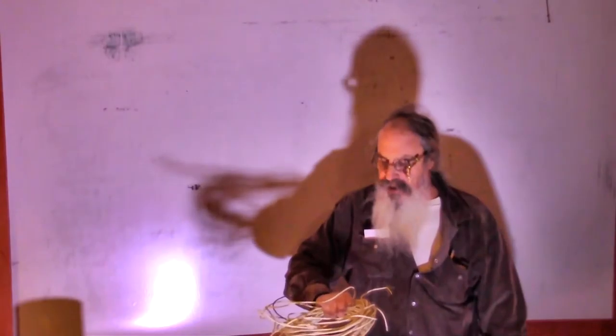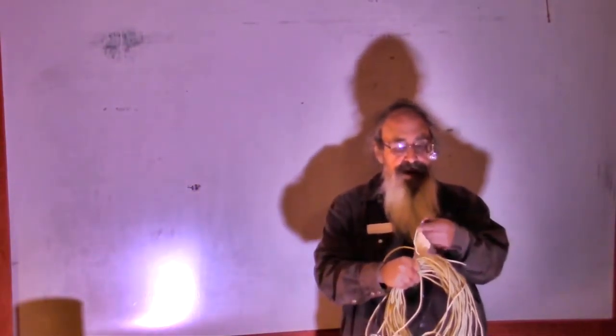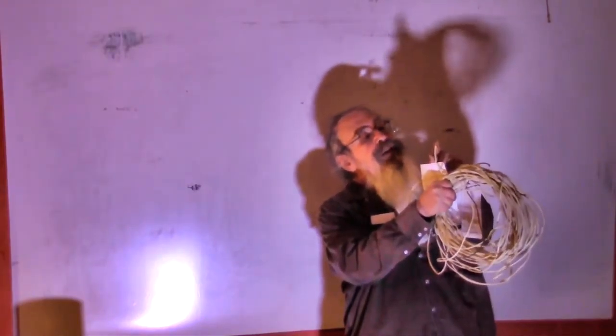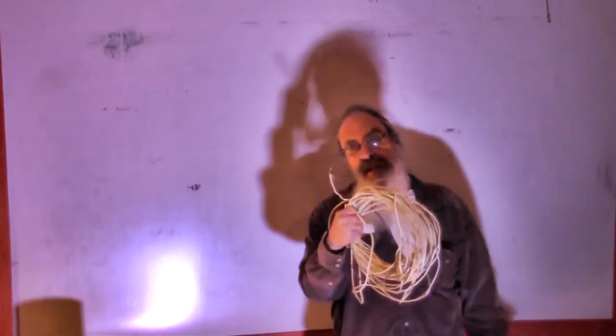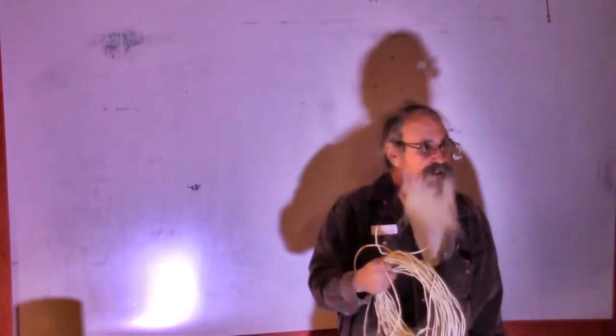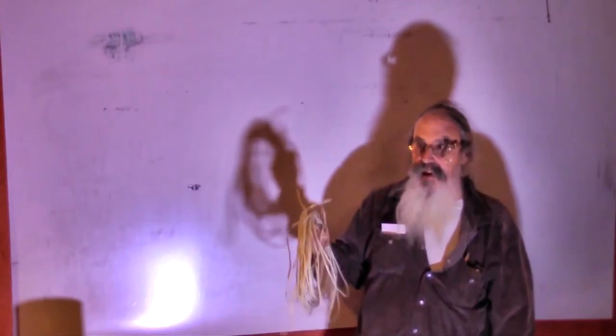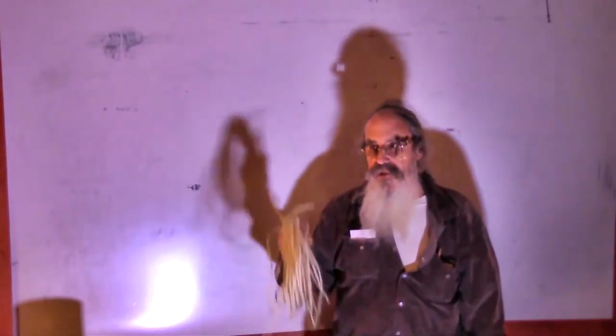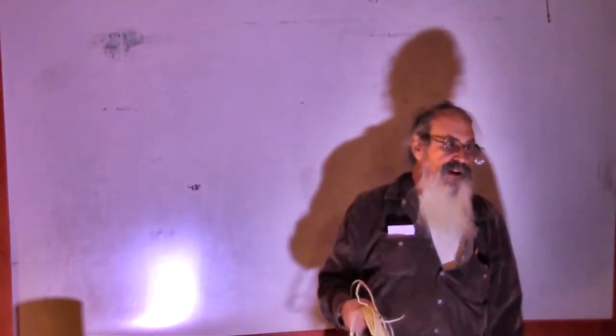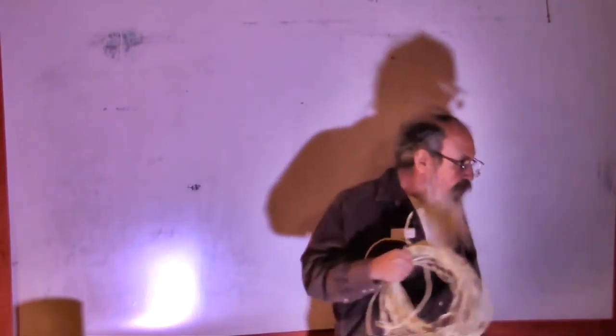So if you want to go a little further, this is not THHN, this is type CW something, which is communication wire. It's actually four wires. You can probably see that tiny little wire there, that's a 22 gauge wire. It's good for telephone. I wouldn't put more than about an amp or two through this. You put too many amps through it, it gets hot, you burn down your house. That's one of the reasons you have to pay attention to amps.